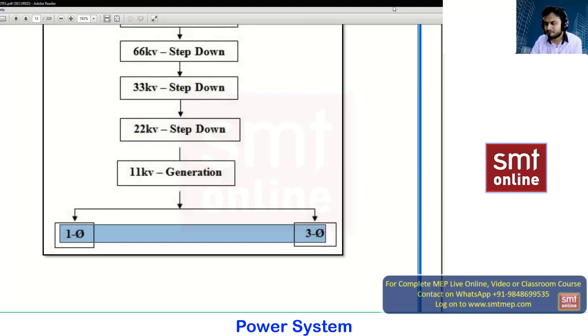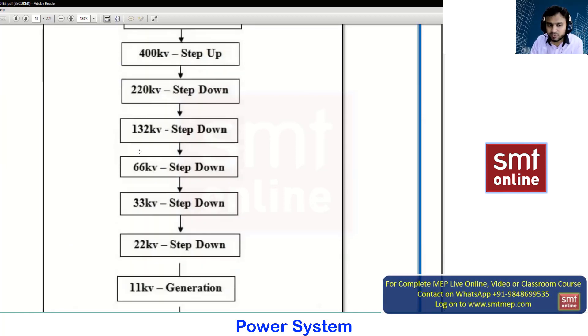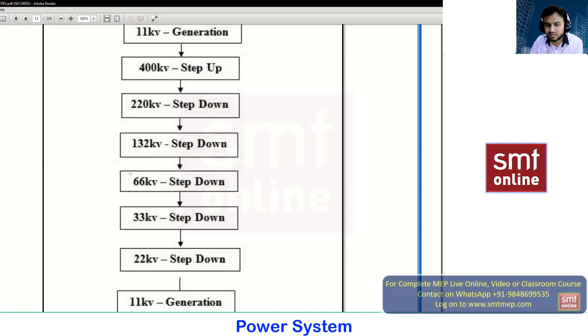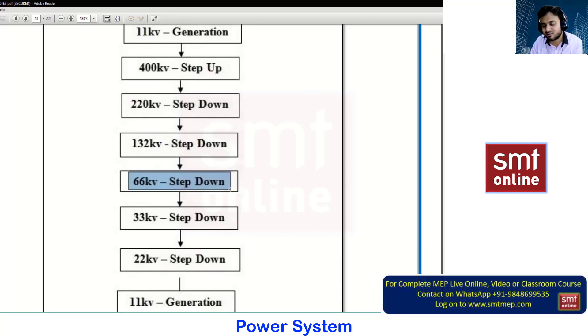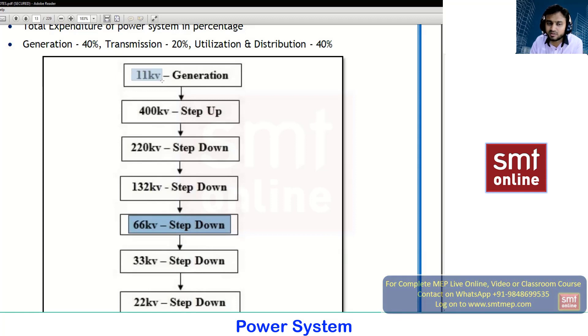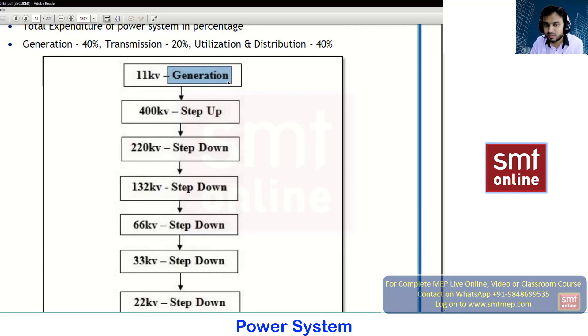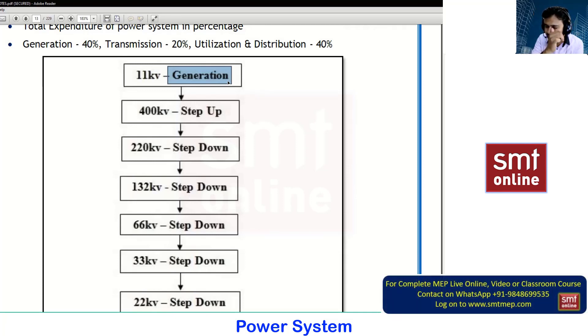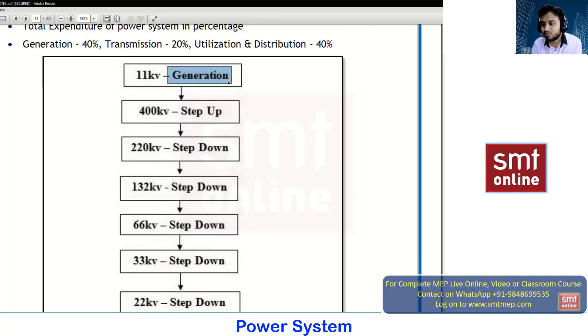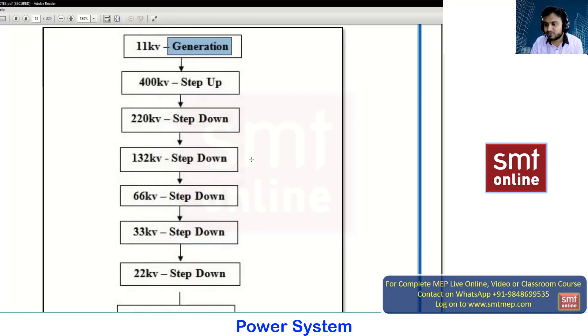No one will generate at 66 or 132kV, because if you generate at that voltage level the initial setup cost of the generating plant will increase. The generating voltage will always be 11kV, or 13.2 or 13.8kV in Gulf countries. If you are directly supplying a metropolitan city — which has commercial malls, super-specialty hospitals, metro rails, industries, and factories — the demand will be more, so we go with a higher transmission voltage.